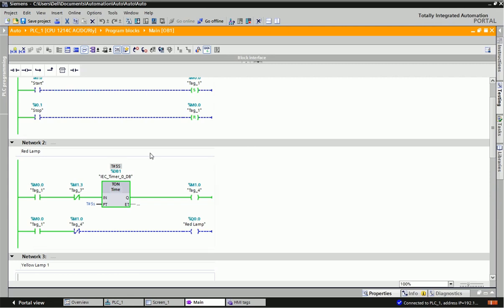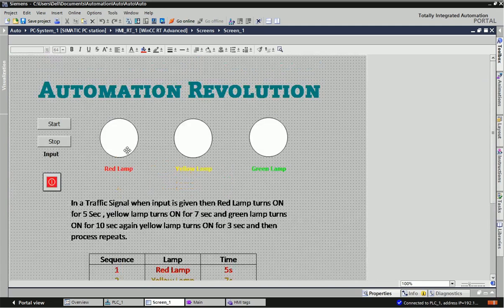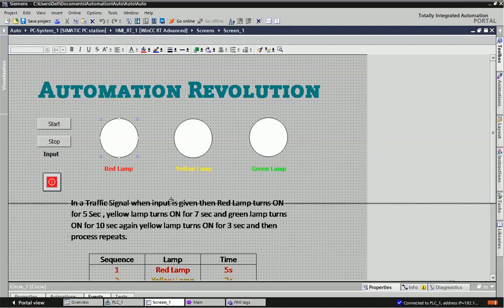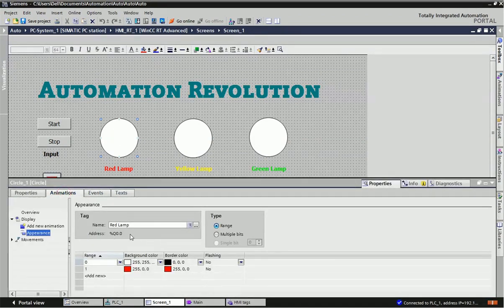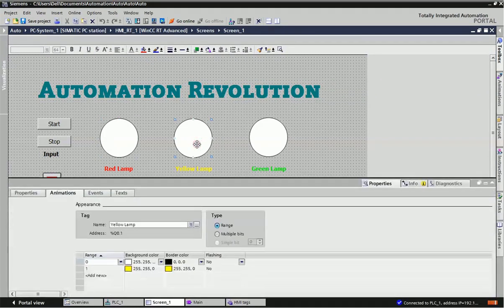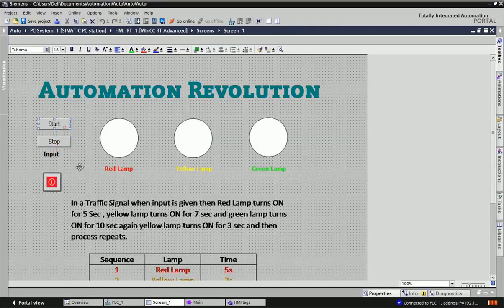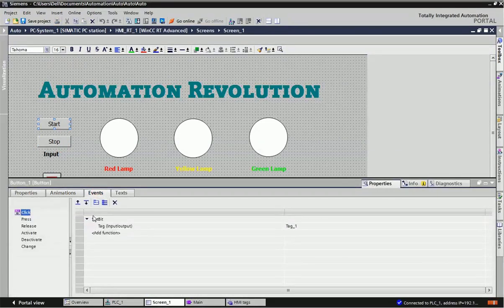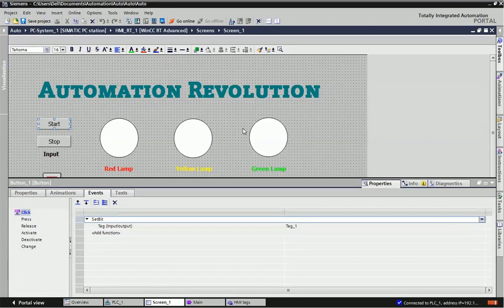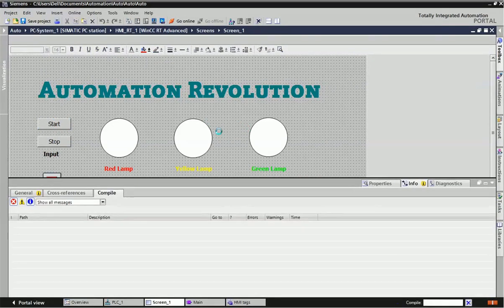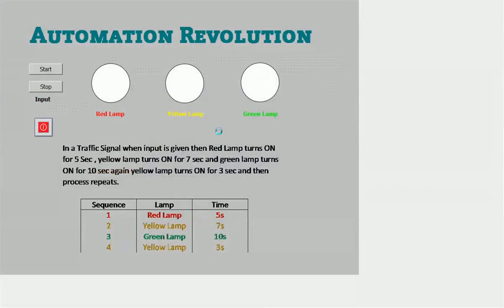Now we can see the program is working in SCADA. Here I have made one screen and assigned tags — Q0.0 for red lamp, Q0.1 for yellow lamp, and Q0.2 for green lamp. Range 0 and 1 is given for color changes. For the start and stop bit we have given an event, and in the event we have made bit set and reset. Now we will go to runtime and see the visualization as per our PLC program.